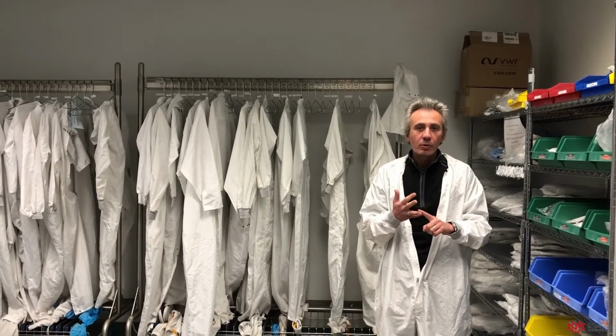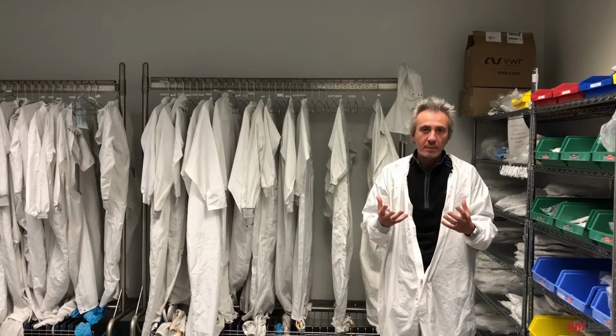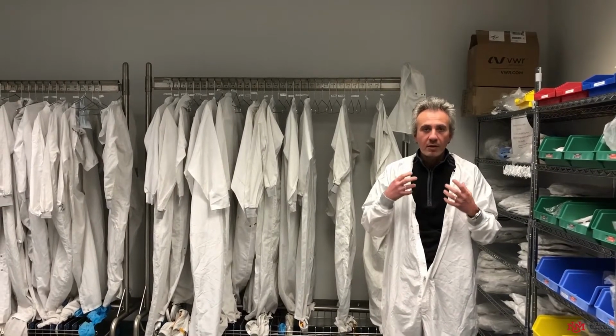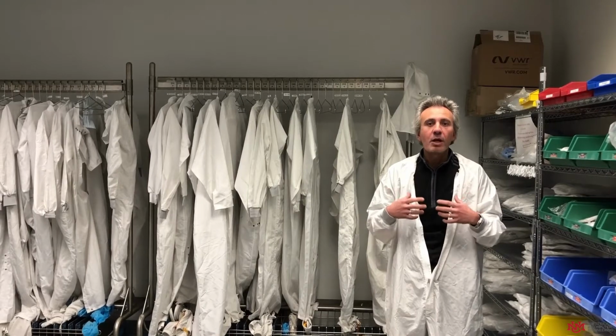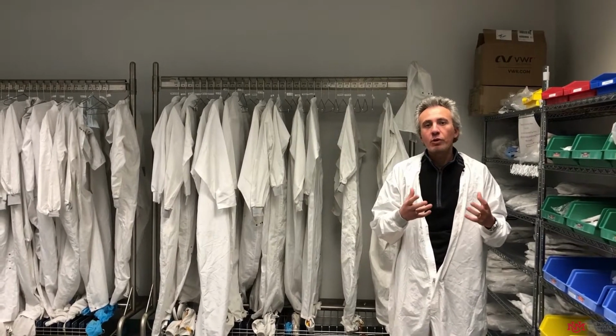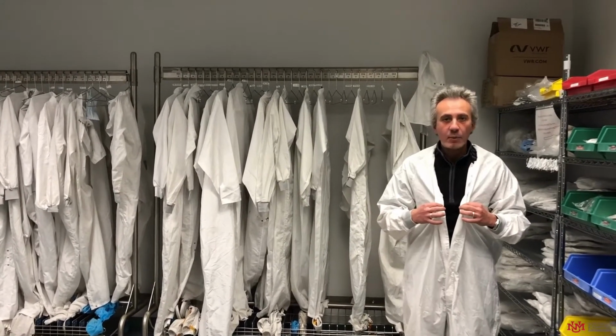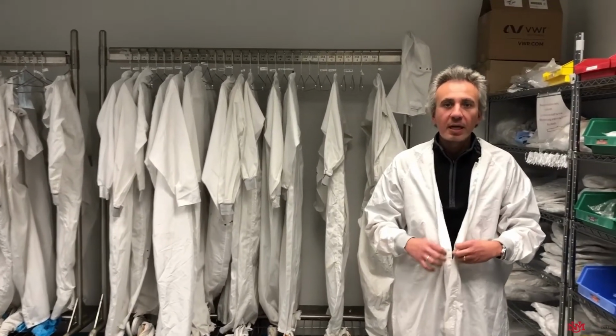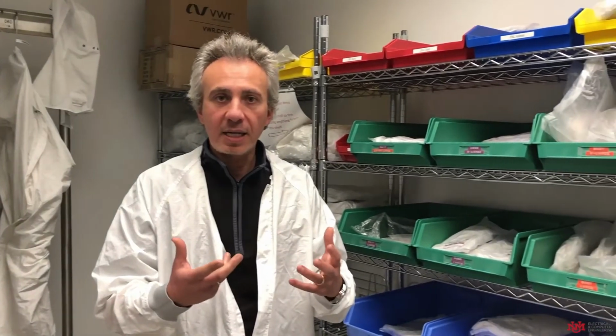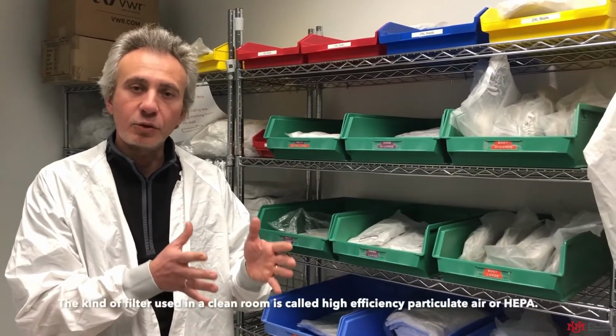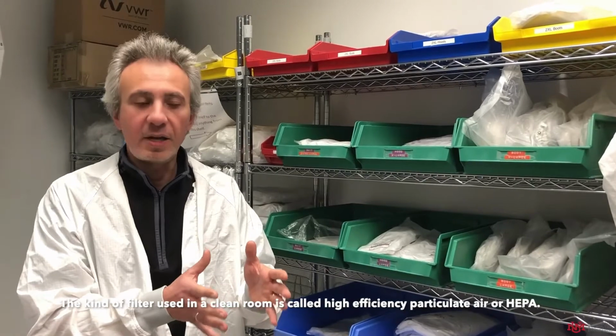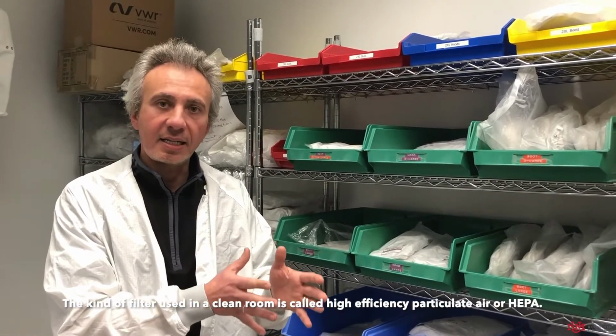The largest pollutant for the clean room is the human body, because every time we walk, from our skin and from our clothes, we lose particles. So in order to control the number of particles, we gown up. We put on clothes that keep inside all the contamination, all these particles that come out from our body and our clothes. In this way, we keep the air clean, and the longevity of the filters, which are pretty expensive, is maintained over a long period of time.